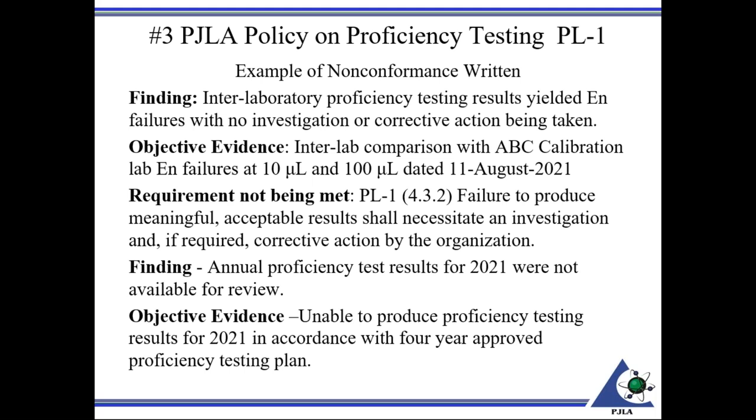Problems sometimes with an interlab test, if it's just bare bones minimum, it's two organizations that are doing it. So if for whatever reason they don't compare, you may be fine, it may be the other CAB. If everything does compare, you're in agreement, you do an E-normal analysis and it shows everything passed, then it's fine. However, if it comes up red, does not pass, you need to stop, investigate and determine what went wrong here, particularly if you did a third party test.